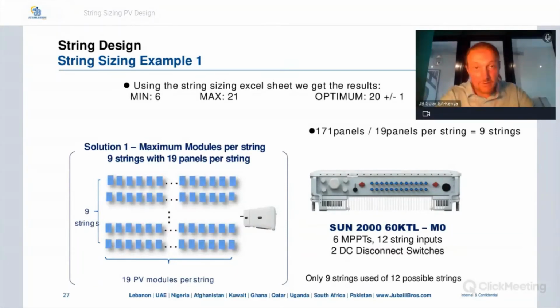So here, the inverter shown there is the bottom of the 60 KTL inverter. So there are 6 MPPTs. Each MPPT can accept 2 strings. So there are 12 string inputs, but we are only going to use 9 strings. So that is okay to have empty string inputs. You don't need to use all of the strings. If you have empty strings, it's okay.